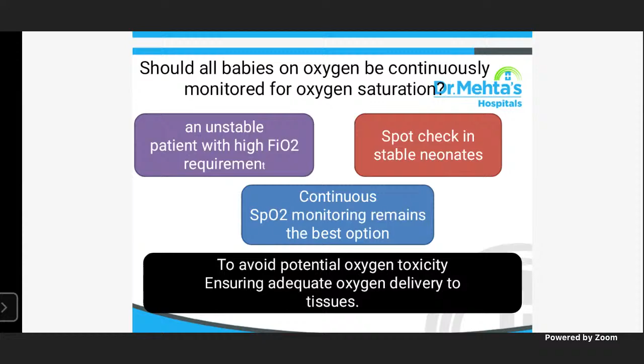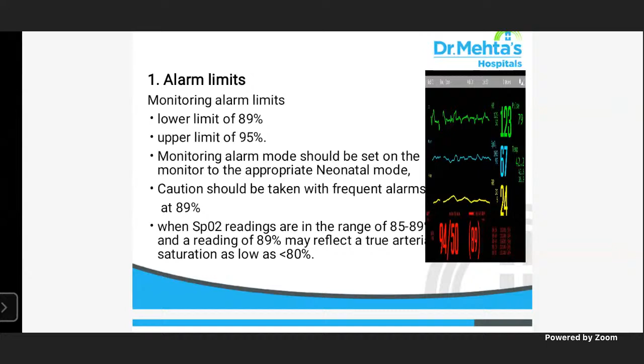Then alarm limits are very, very important. At the beginning of each shift, we have to set the lower limit and the upper limit. Then only can we identify a sick neonate, whether the baby is having any problem or not. So lower limit 89, we can set upper limit 95. It should be set appropriately. Many monitors have an adult mode and a neonatal mode, so we have to set the neonatal mode. And for readings in the range of 85 to 89, a reading of 89 may reflect a true arterial saturation as low as less than 80%.